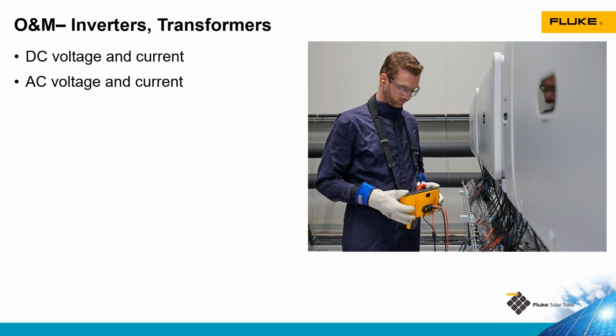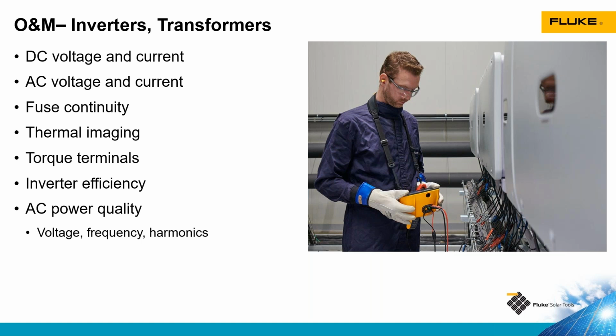Now, our inverters and transformers are going to need operations and maintenance as well. We can do DC and AC voltage and current testing. We can check things like fuse continuity. We can do thermal imaging. We can torque our terminals, make sure those haven't loosened over time. We can calculate inverter efficiency. And we can also do AC power quality measurements, like making sure the voltage and frequency are within specifications of the inverter. We can look for harmonics. With the higher end power quality meters, we can also check for transient voltage spikes. We can data log and see those spikes coming.